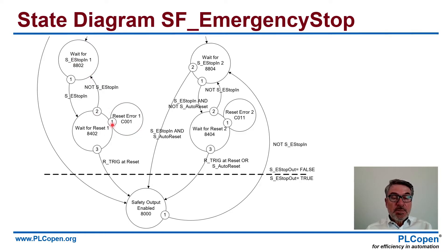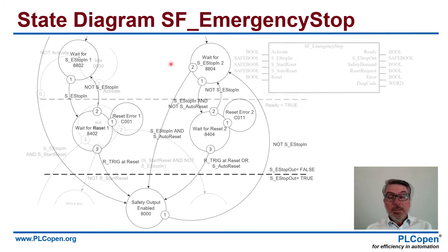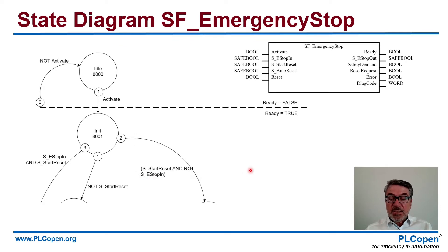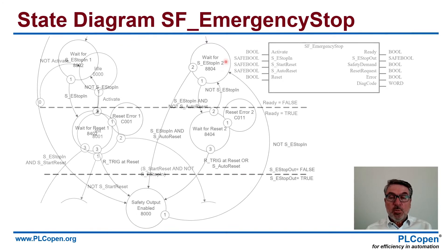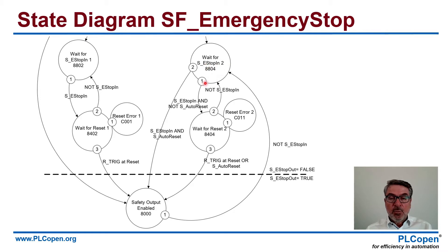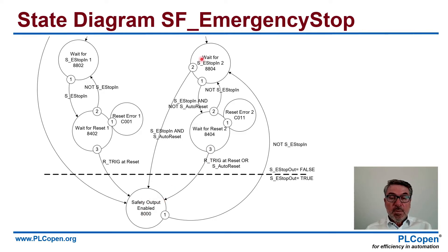A reset error is always priority one. The other one is start reset and not e-stop in. So what you get here is we wait for e-stop in. We enter state 8804, and if e-stop in is there and there is no auto reset, we wait for the reset. There can be a reset error — priority one. Or if the reset gets there, the R_TRIG at Reset or auto reset, we move to the safe state. The shortcut is: there is an e-stop in and there is an auto reset, and we immediately go there. There is one way out — not e-stop in. We remove the e-stop in and wait again for e-stop in.